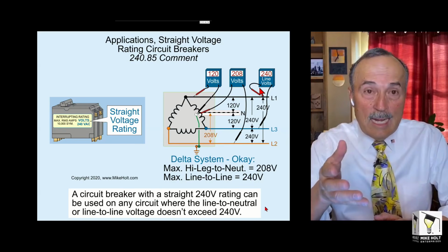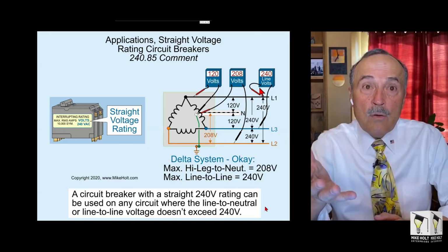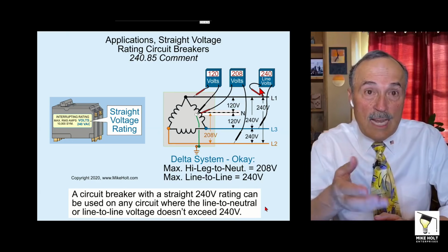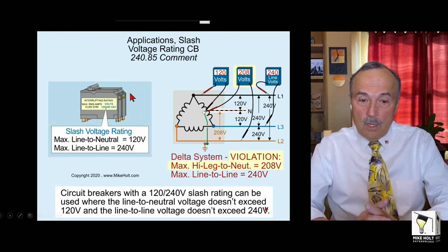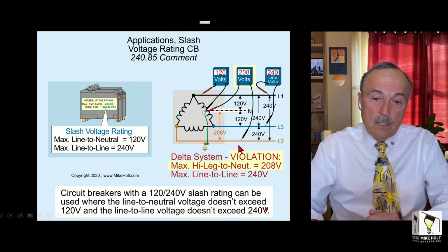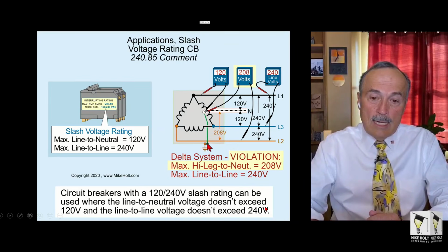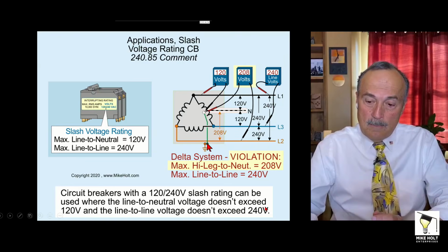Now, if you don't put it on the high leg and you go to line 1 and line 3 only, well, then you can use slash rated breakers. And here's just an example where if you had a slash rated breaker and you connected it on the high leg, well, then that would be a violation.